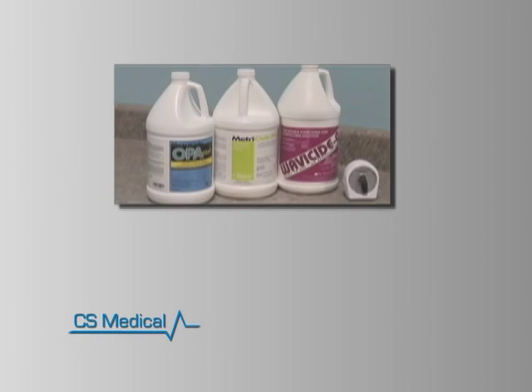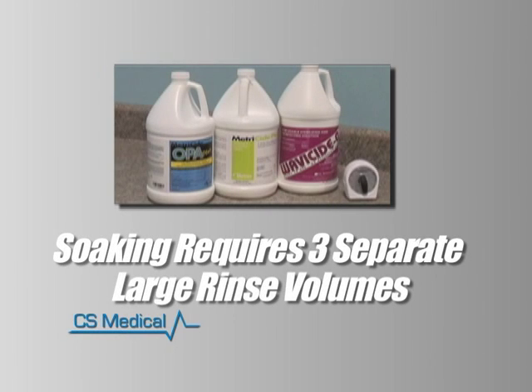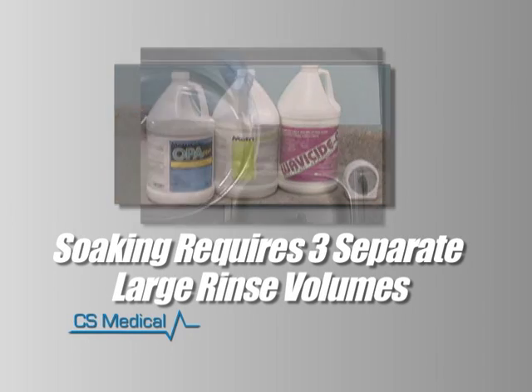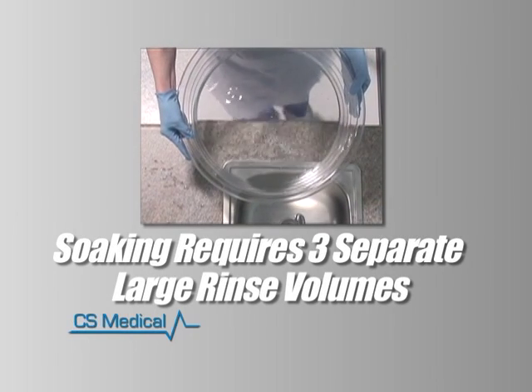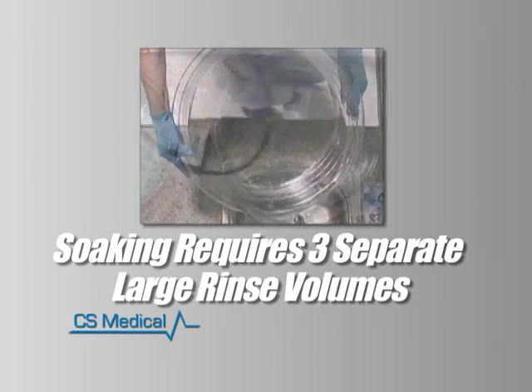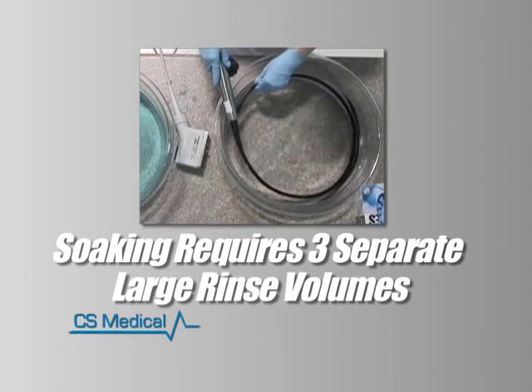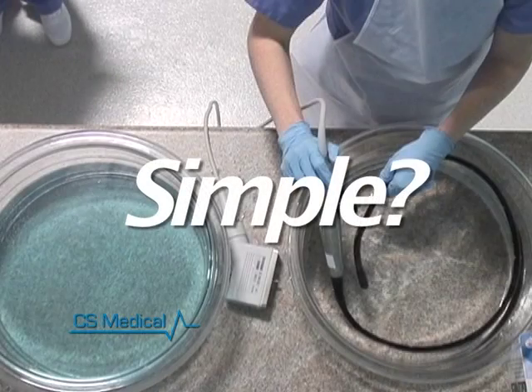Regardless of how you soak your TEE probes, both glutaraldehyde and OPA require 3 separate, large rinse volumes, 2 gallons or more, using fresh water each time. Each rinse requires at least 1 minute of immersion. Sounds pretty simple, right? Well, here's what you actually have to do.